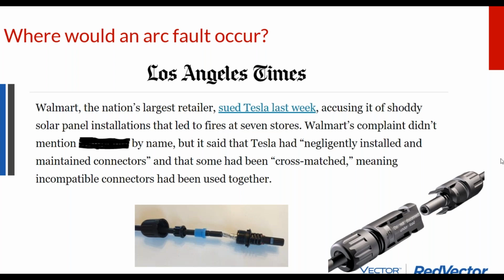And so in the solar world, we have this black connector on the right called an MC4 connector. And if that connector is not plugged in with a solid snap, or if they messed up the insides of the connector where it's supposed to be a male and female metal piece, but they look very similar. So they accidentally crimp like a female to female, and they try to shove the connector in, and some of these construction guys are so strong they can make it fit, sort of, and you could get an arc fault within this MC4 connector. So arc faults occur within the line.